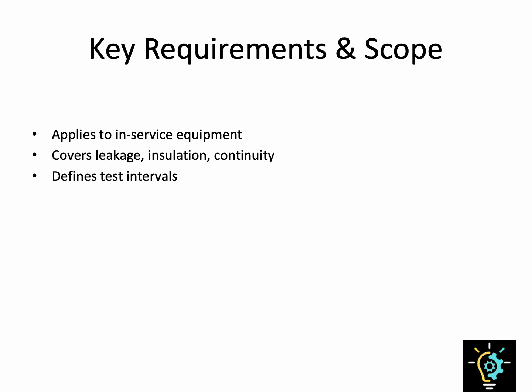But there are some critical differences from IEC 60601. First, IEC 62353 avoids destructive tests that could damage the device, things like high voltage dielectric testing that aren't part of the routine. Second, there's no preconditioning of equipment. There's no artificially elevated mains, and tests are performed under single fault conditions only. The focus is on ensuring ongoing safety without introducing unnecessary risks.